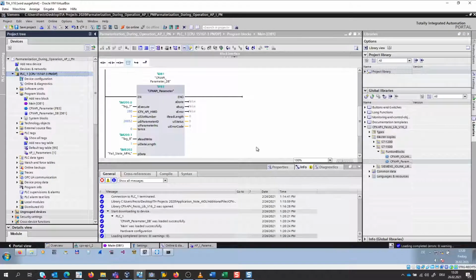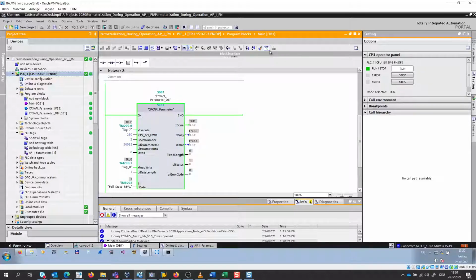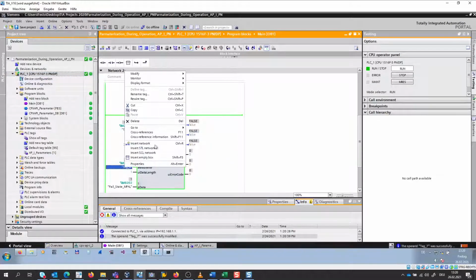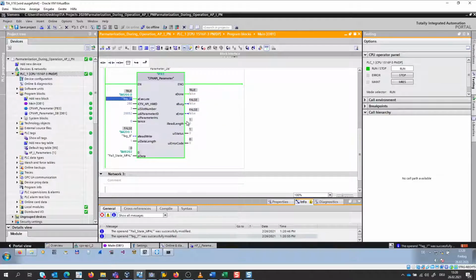After a few seconds you will recognize that everything is running, and I can use the block inside my OB1 with the monitoring function for testing purposes. First of all, I move this block off, and this block here also off, making this variable 0 again, and let us test the read functionality first. To read, this has to be false. I'm activating the block now, and you see I received the read length as 1 byte, the status 1 means everything fine, and the value is 0.